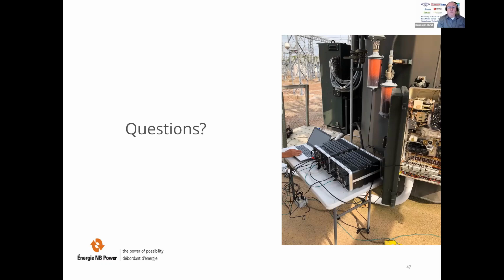Okay. I have another question. Is there an advantage to tapping the transformer windings at the three levels, high, mid, and low, as opposed to all legs being tapped in the middle? What? In fact, what I understand of your question is that you want to have just one tap. For example, you have 33 taps, and you put your tap in the middle, right? Well, that's the question. Peter Nichols asked it: is there an advantage to tapping the transformer windings at the three levels, high, medium, and low, as opposed to all legs being tapped in the middle? I guess having the three levels tapped separately as opposed to having them all tapped in the middle.